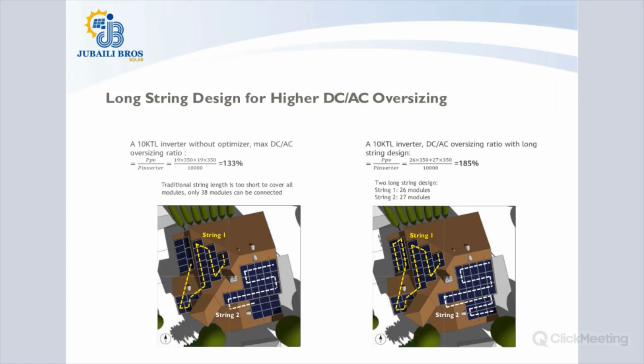So let's take a look at the application. How are we able to apply the long string design for high DC and AC oversizing? So you take a look at this roof on my left, and clearly you could see that without the optimizers, this is traditionally the maximum string length we could do. String 2 also can give us a maximum of that. But with the longer string design, we could add more modules in order to fill the spaces on the roof without any significant degradation in the power that the modules produce.